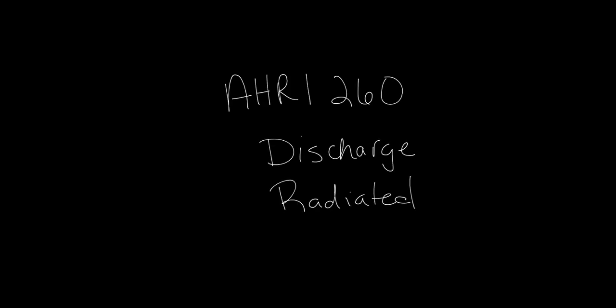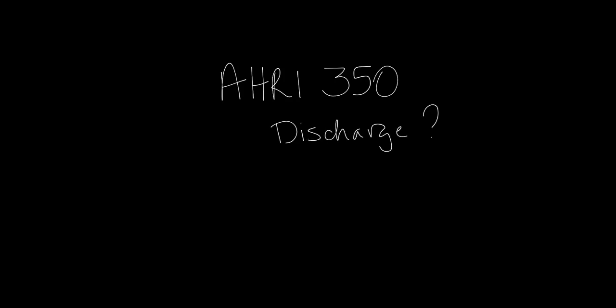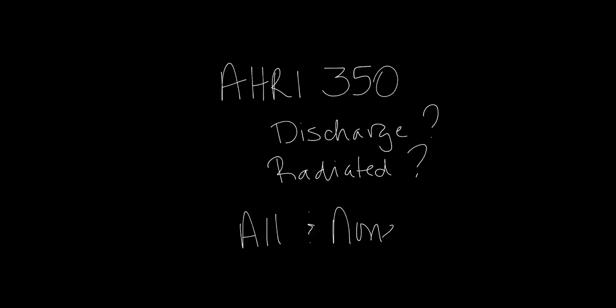With VAV products and fan boxes, they are under the AHRI 260 testing standard that provides two numbers, discharge and radiated sound data. Fan coils, on the other hand, follow a little bit different standard, which is AHRI 350. Under 350, you might ask, so are we going to get discharge, radiated sound data? You know, what kind of sound data are we going to be provided with? Well, the answer is all of them and none of them.